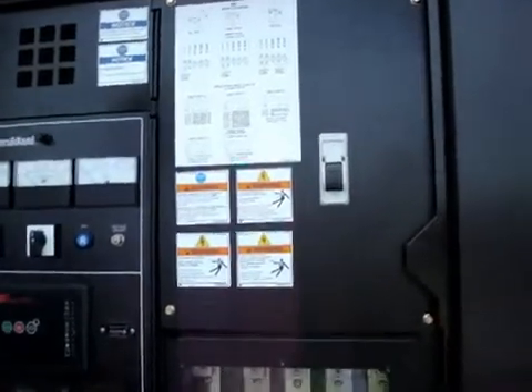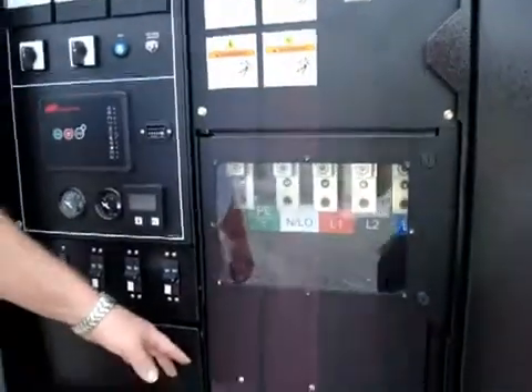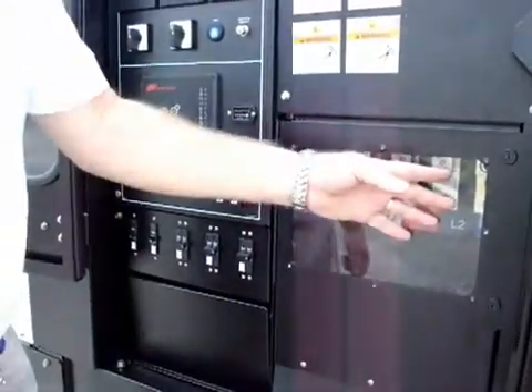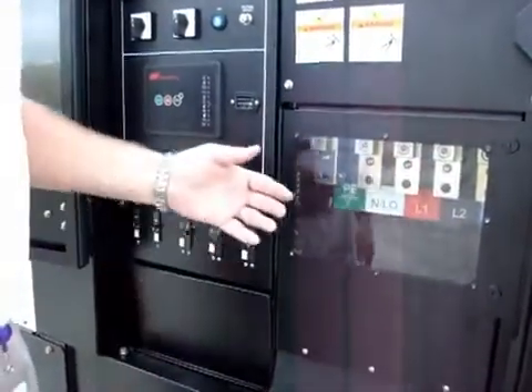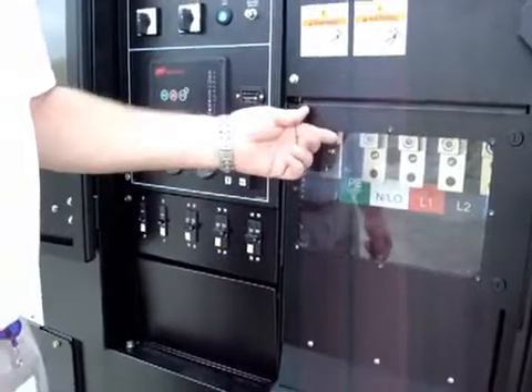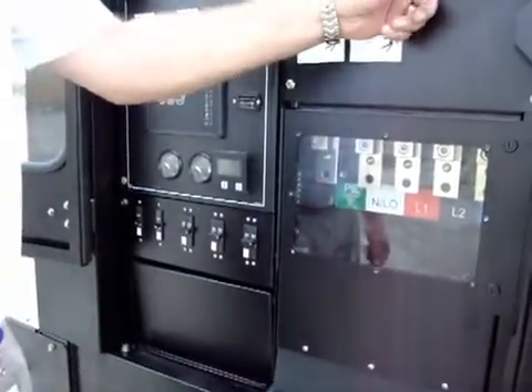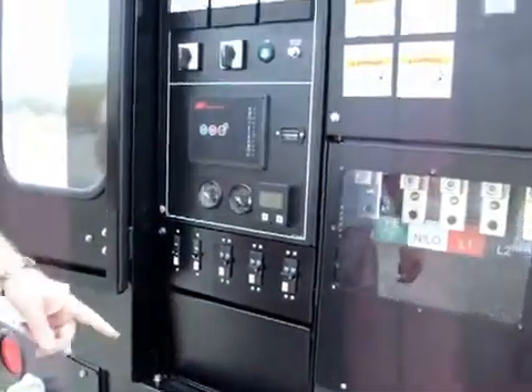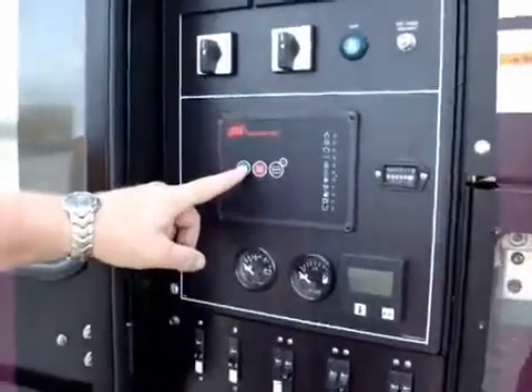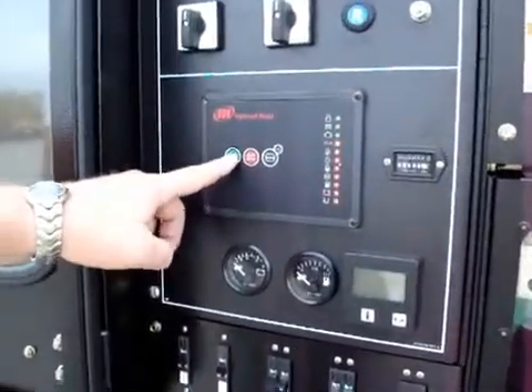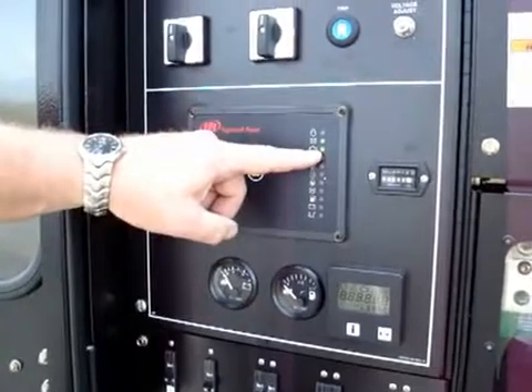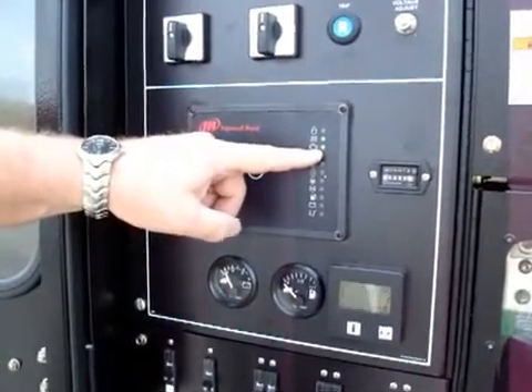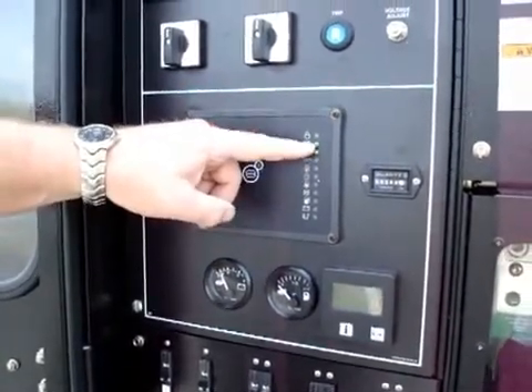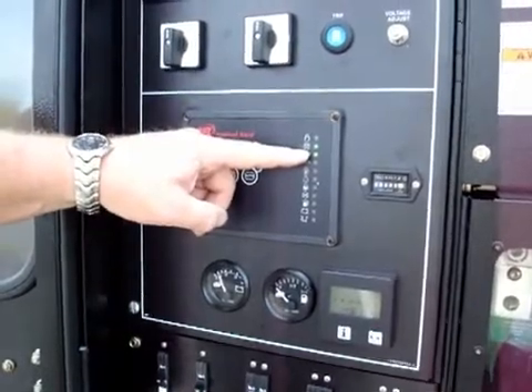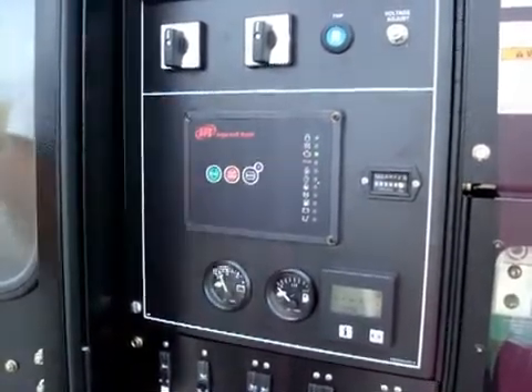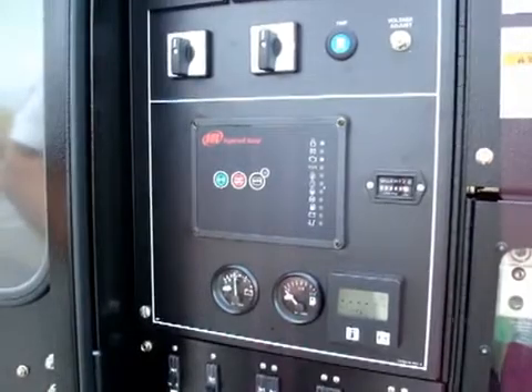Next step would be to verify any of our loads are connected, all the connections are properly connected, proper grounds are installed in accordance with the local code requirements, and verify that the breaker is open. The next step is to press the start button. We have a green light for the ECU, tells us that everything is good with it. We have a green light for the pre-glow, which will last for 10 seconds before the engine starts and runs.